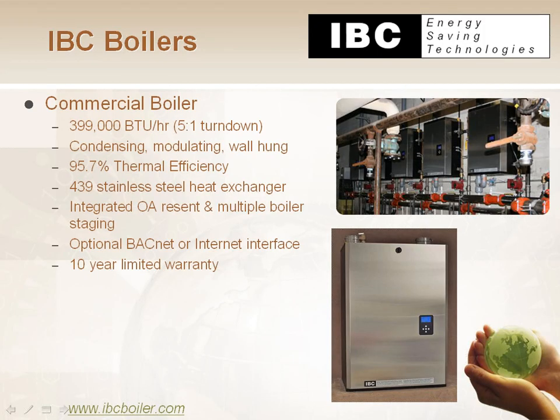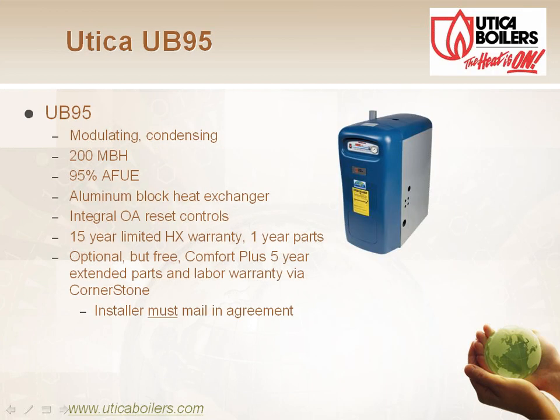And then there is a commercial version of that boiler, 399,000 BTUs, and it's a 95.7 thermal efficiency. Similar type controls, outside air reset built in, multiple boiler staging. I think you can stage up to like 24 boilers off of his standard controls. And there is an option for a BACnet output if you're trying to tie this into a building automation system and get some more data off of him.